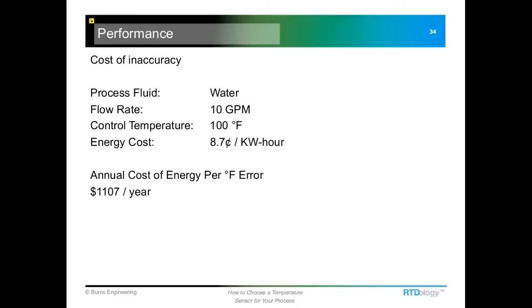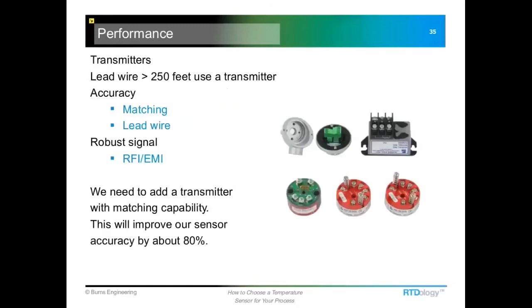Yeah, or on the other hand, if you're not heating it enough and you end up with bad product, that can cost a lot too. The bottom line, though, is that it really pays to get the most accurate temperature measurement that you possibly can for the process. Now, we've got already that 1.6 degrees Fahrenheit error, plus we've got our sensor interchangeability number. So we're already way over our little budget, and then we're going to be putting a transmitter in here too.